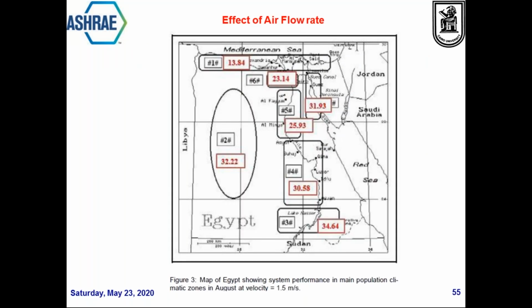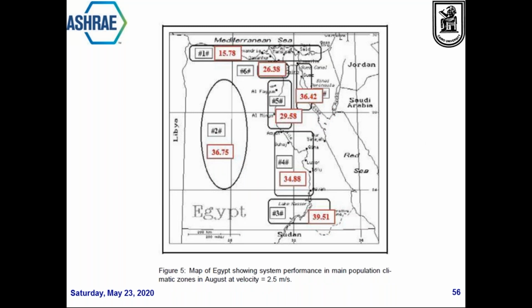Now, as I promised you, I will be speaking about the effect of the airflow rate. So instead of an average velocity of 0.7 meters per second, we raised the air coming to the section to 1.5 meters per second. And here in August, we see that the energy efficiency ratio increased. Then we increased it further to 2.5 meters per second. 2.5 meters per second is the classical design air velocity that we use when we are doing air handling units. And here we have a further increase in the amount of energy that we save.